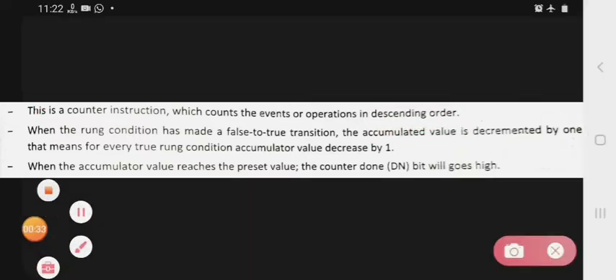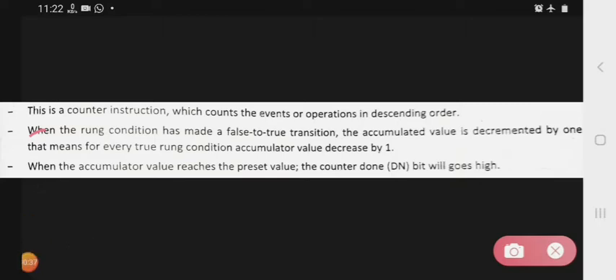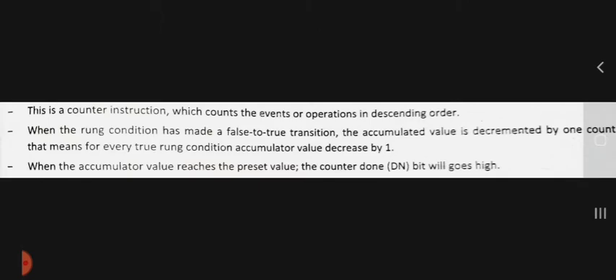When the rung condition makes a false to true transition, the accumulated value is decremented by one count. That means for every true rung condition, the accumulated value decreases by one.